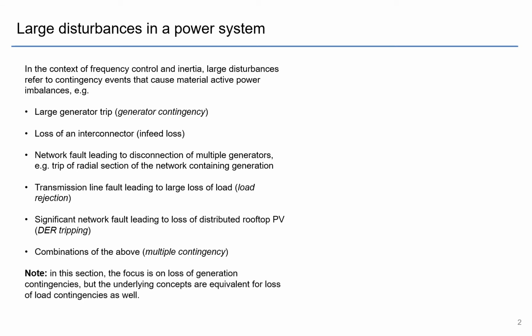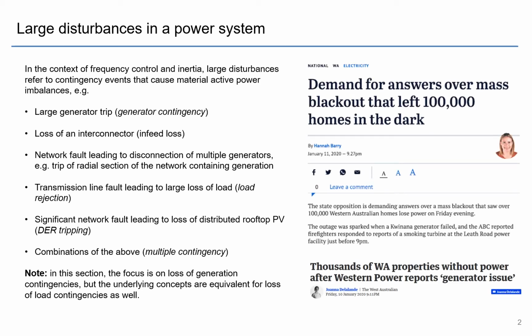So in this section, we're really going to focus more on the loss of generation contingencies, but the underlying concepts are equivalent for loss of load over frequency events as well. And this is what happens when we all get it wrong. Earlier this year, we had a large generator trip event. It was actually a multiple contingency that caused under frequency load shedding, and as the news stories report, there were about 100,000 homes that got blacked out.